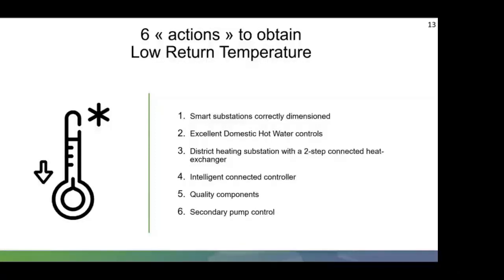Using a 2-step connection enables the use of recirculating residual heat in the building to preheat the domestic water on the heat exchangers, making the substation more efficient. So any waste heat in the building that's not used on heating could potentially be used to preheat the cold water coming in for domestic hot water.